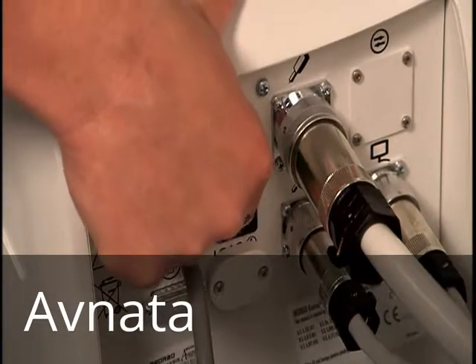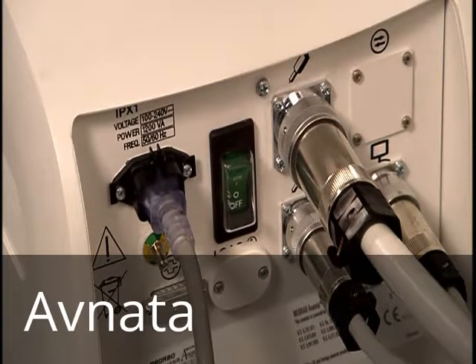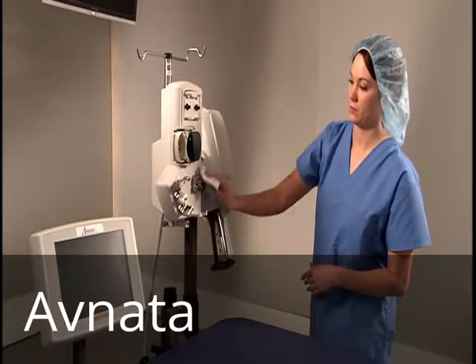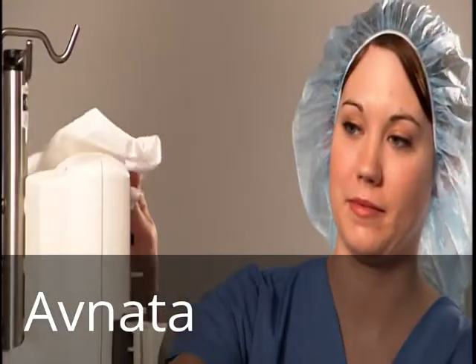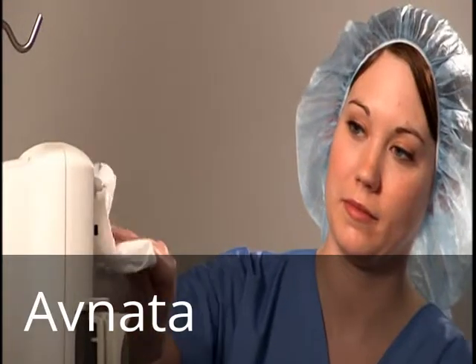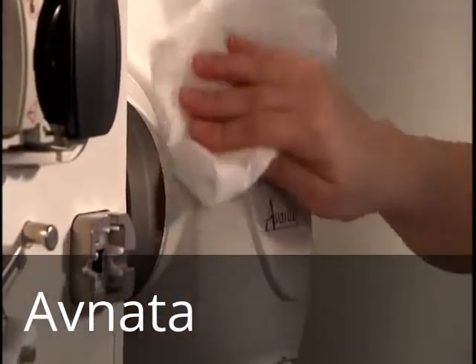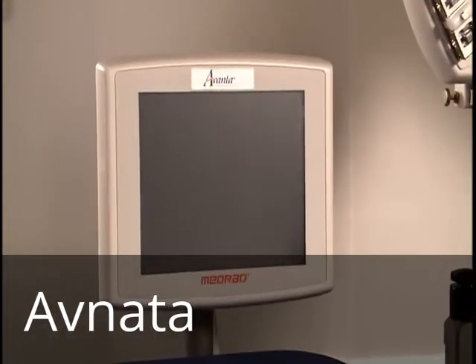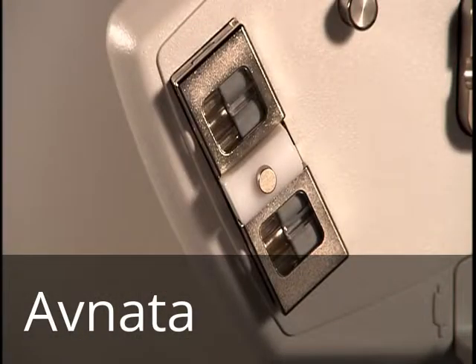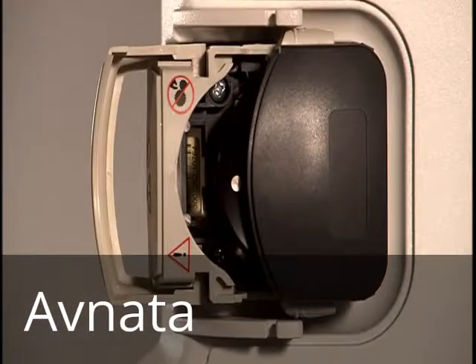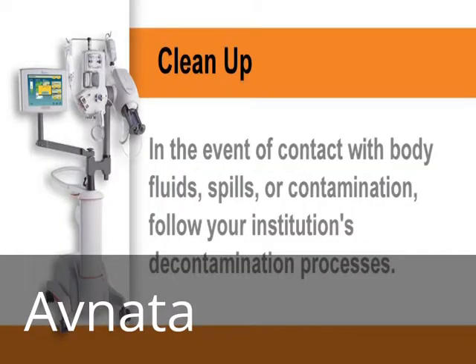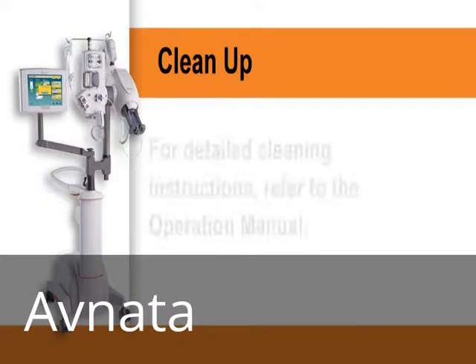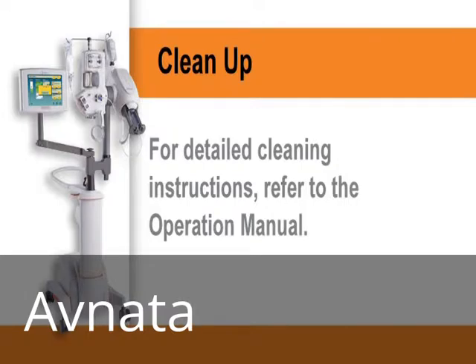To clean the Avanta Fluid Management Injection System, disconnect it from the power source. Clean the system components using only a soft, non-abrasive cloth dampened with mild cleansing agents or water. Never use abrasives or harsh chemicals. Avoid spraying cleansers directly on the components, particularly the touchscreen. When cleaning the FCM, ensure that the backlighting on the drip sensor chambers, the gross air detectors, the CFCV, and the peristaltic pump are free of contrast buildup to ensure proper operation. In the event of contact with body fluids, spills, or contamination, follow your institution's decontamination processes. For detailed cleaning instructions, refer to the operation manual.